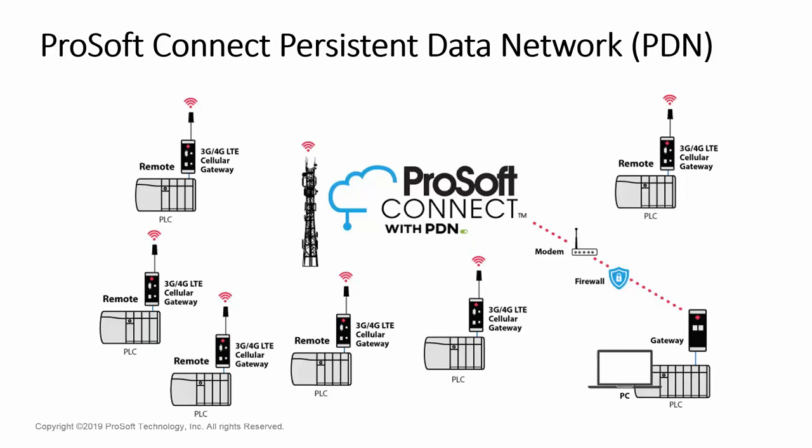That's a great question. Thank you, Mr. Sandhu. So we actually have a very similar application today running here in the New England area, where the customer's got about 12 to 14 pump stations that they're monitoring, and they're bringing back 100 points as well. They are polling these remote sites every 10 seconds, so that's your frequency, and their data usage per month on these sites is about a gig of data.